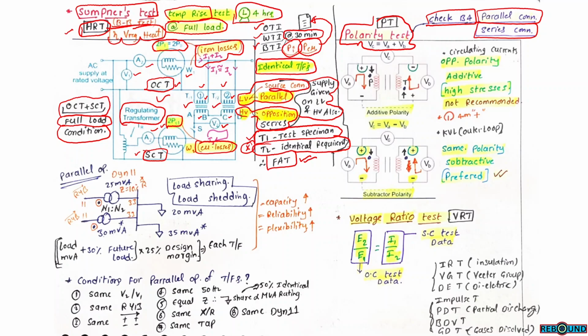So these are the approximate diagrams for additive polarity and subtractive polarity. This is the primary side and this is the secondary side. On the primary side, we are assuming a dot and this is the current direction. On the secondary side, we are assuming a dot and this is the current direction. Here we are assuming that for this current to cross this winding, it takes time t seconds. On the secondary side, this current also takes t seconds to cross the total winding. On the primary side, the current is entering from the top and it takes time t. On the LV side, the current is entering from the bottom and it takes time t to reach the top.